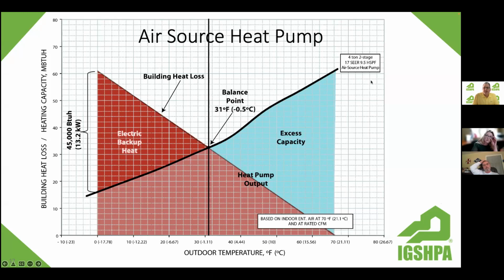This happens to be a 4-ton, 2-stage air source heat pump. It's 17 SEER cooling efficiency and 9.5 HSPF heating efficiency. And you can see the capacity as the outside temperature drops, goes down, which we would expect. This line right here is the building heat loss. As I mentioned earlier, this example I used was 61,000 BTUs per hour heating, heat loss at 0 degrees Fahrenheit outside. So when you compare what the building needs to what the heat pump can provide, that's how we come up with this balance point. At 31 degrees outside, the heat pump capacity can still heat the home, but when it's below 31 degrees, then all of a sudden we need this red area, we need some backup heat. And at design conditions, in order to heat that house, even though it's only 2.5% of the time of the year, we have to bring in backup heat in order to satisfy the thermostat.